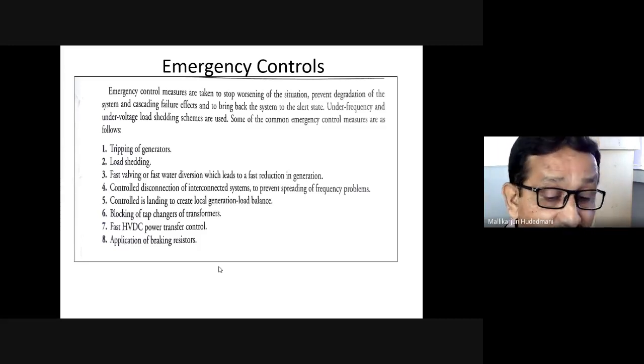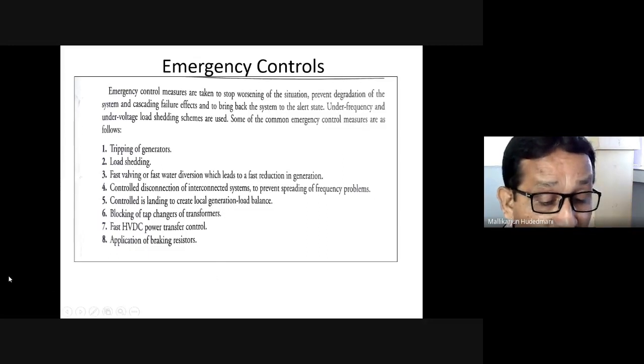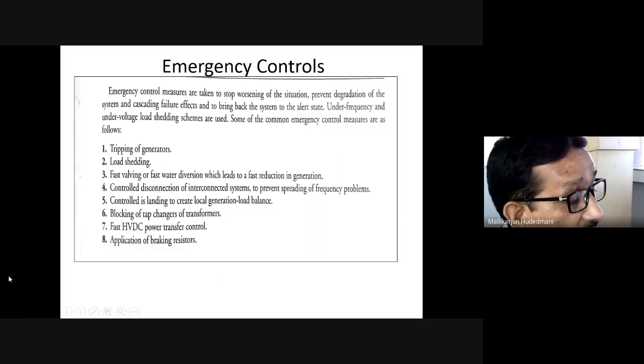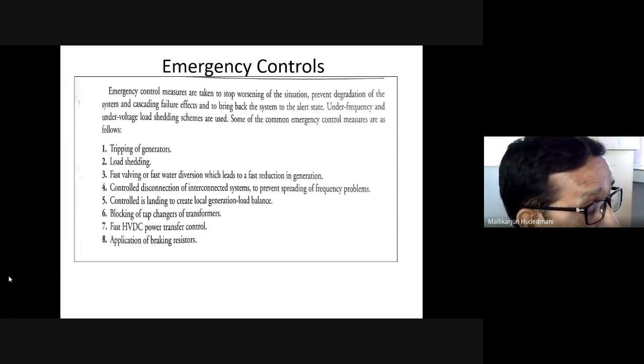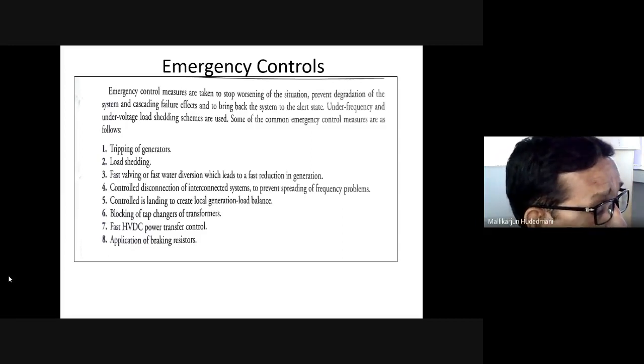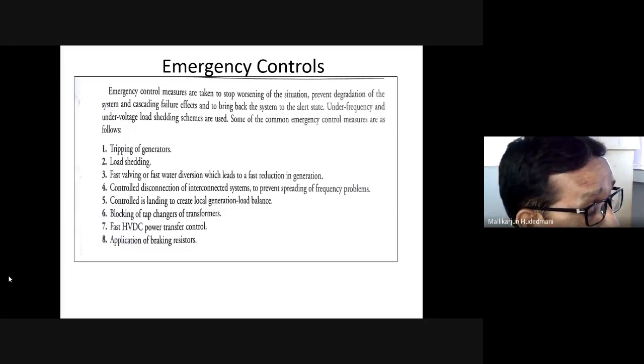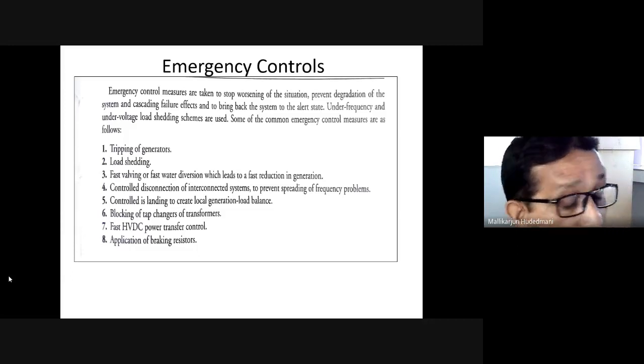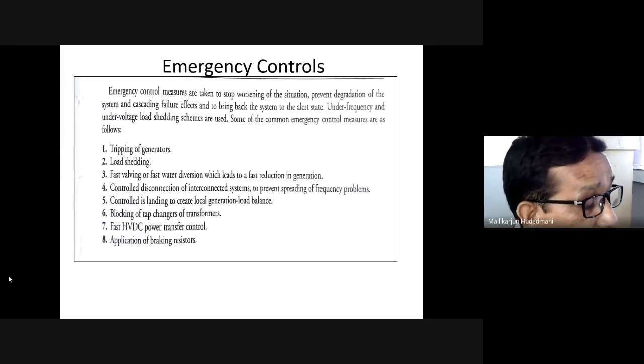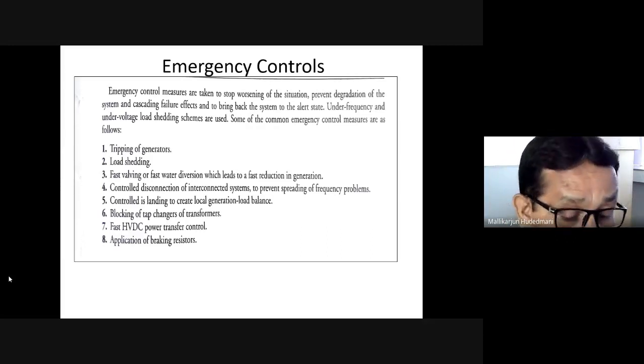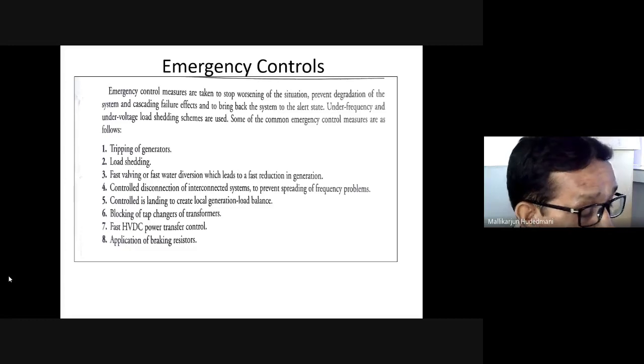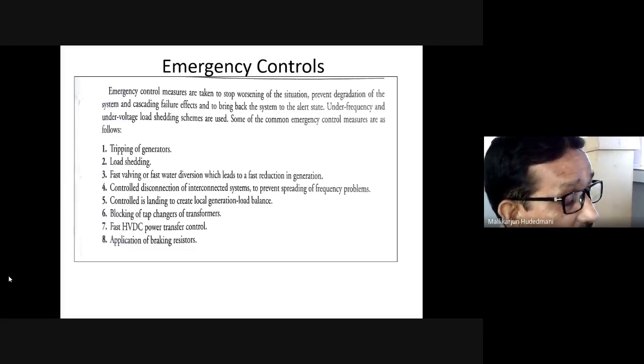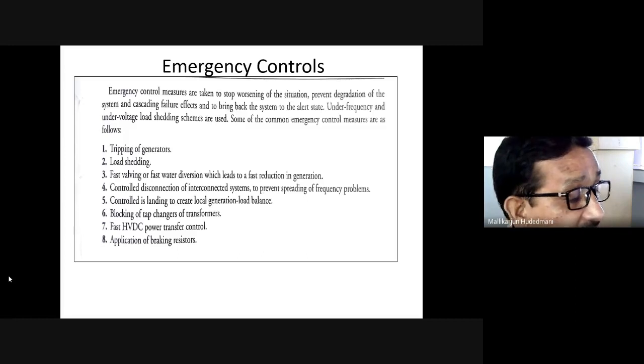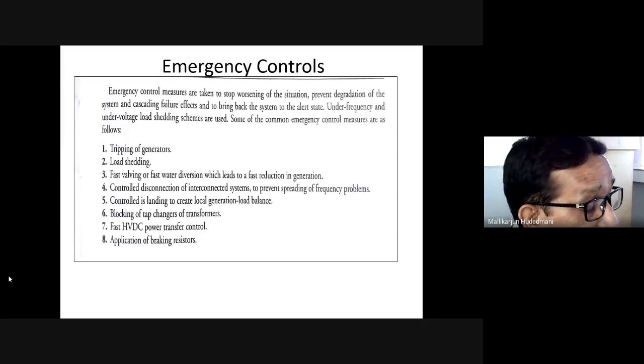The rotating mechanism, with a high mass and high centrifugal forces, will make the parts fly away from the rotating mechanism. Therefore, they need to be appropriately cut in. Braking resistors are the ones hooked across the armature of the synchronous generator to bring that entire excess power which is floating and dump it to the earth, so that these resistors facilitate breaking the generator terminal into ground, so that the generator comes to a halt very fast. Hence the name braking resistor.